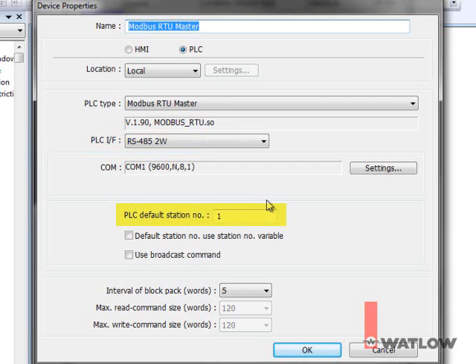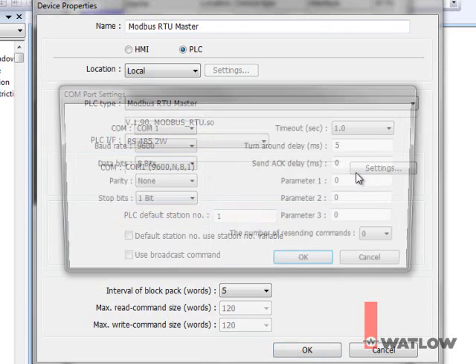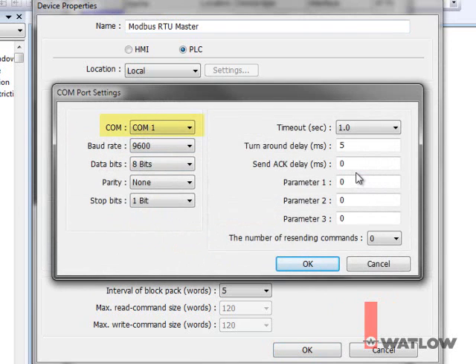Set PLC default station number to the Modbus network address of one of the RM controllers. The default setting 1 is good since we have a control module at address 1. Click Settings, and for COM, select the port on the OIT to which you connected the RM controller. In this tutorial, that's COM 1.